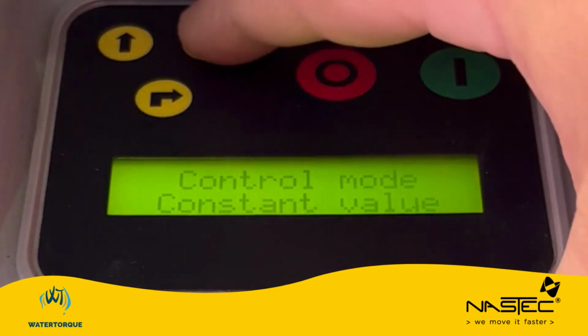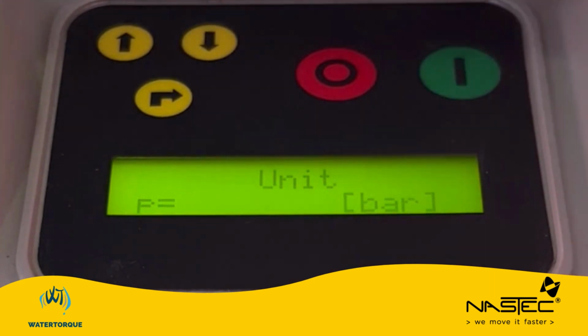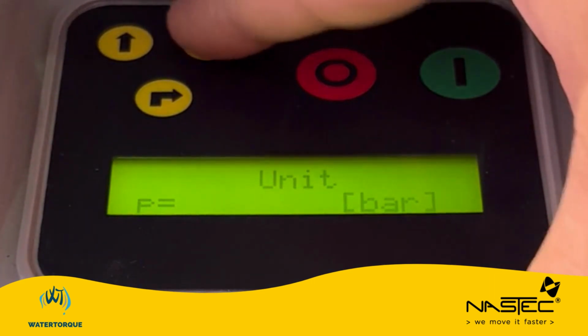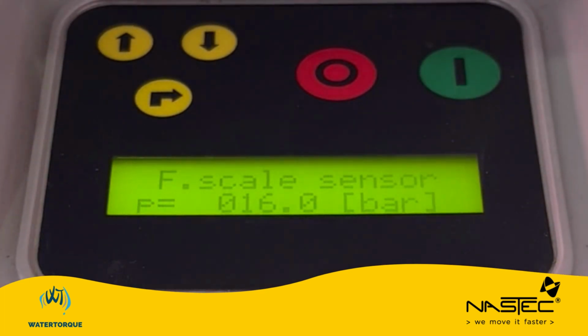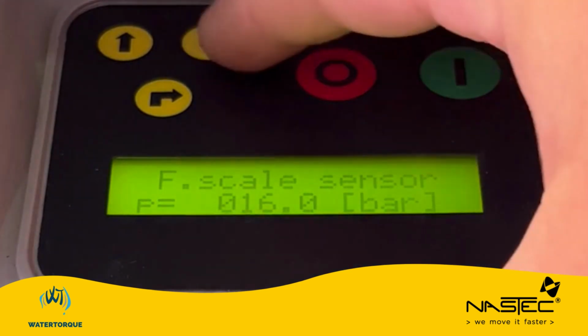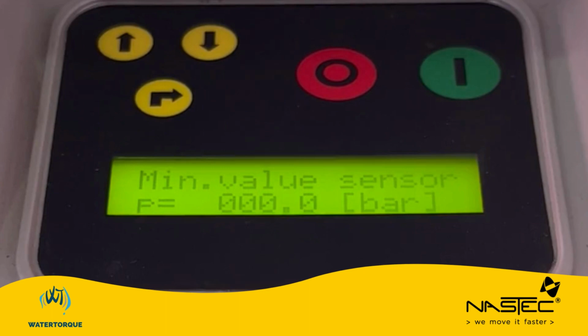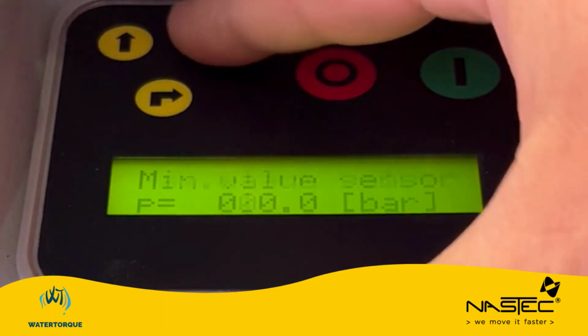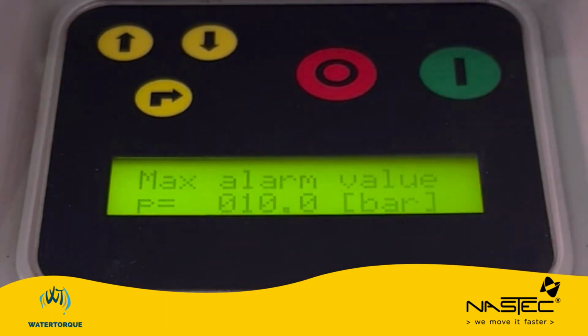From here, we hit the down arrow. That's the units, which are measured in bar with our pressure transducer. F-scale sensor also refers to the pressure transducer, which is a 0 to 16 bar pressure transducer. That's the maximum, and that's the minimum of the pressure transducer. Max alarm value is the pressure at which we want the pump to shut off. This particular pump has a maximum head of 5 bar and a minimum head of 2 bar.